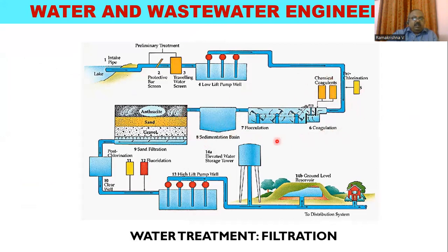This is a later component of the treatment system. We'll talk about sand filtration. This filtration is carried out through a filter bed — a filter medium of sand — with gravel kept as the supporting medium. At the bottom, a strainer with openings and perforated pipes are placed. When raw water is passed through this bed, it passes through the voids of the sand and through the larger voids of the gravel.